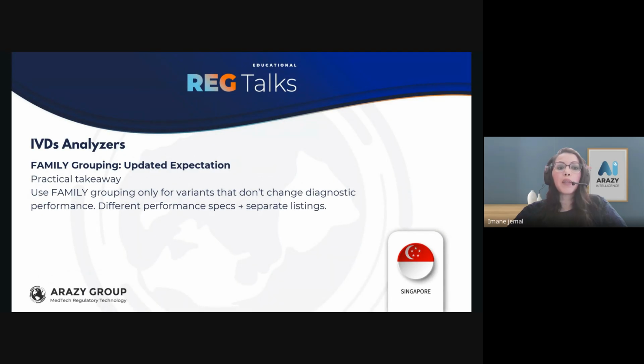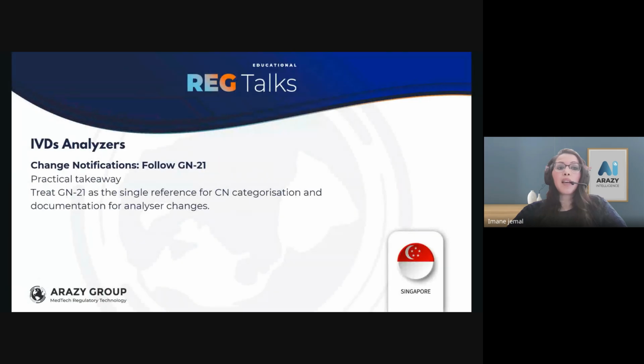Regarding family grouping, what is expected in this update? This revision 2 tightens grouping. Performance differences mean separate listing, even if the instrument looks similar commercially. So use family grouping only for variants that don't change diagnostic performance. If there is a difference in the performance, they should be listed separately. This is the second update in this IVD analyzer guidance.